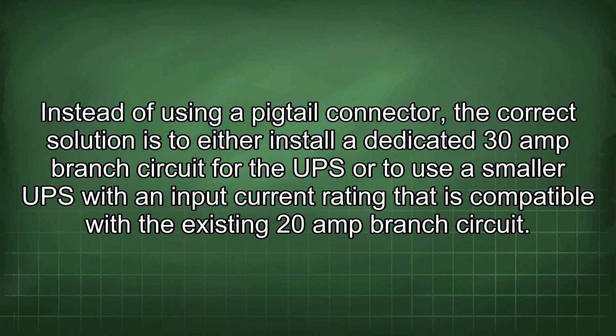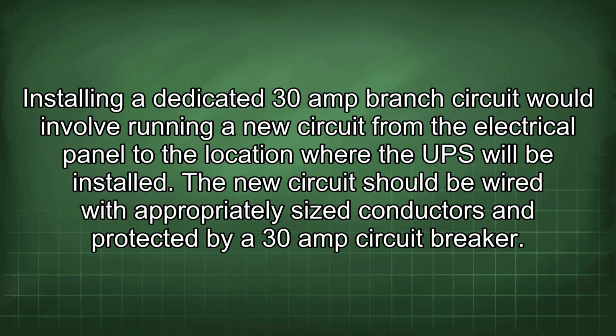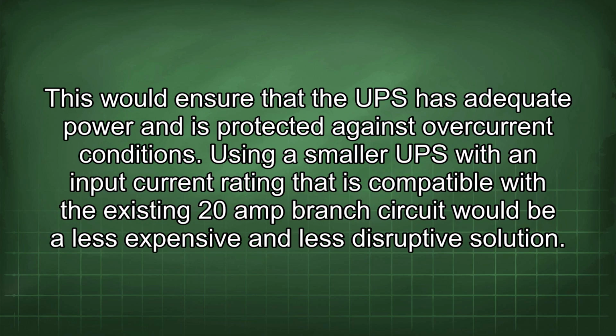Instead of using a pigtail connector, the correct solution is to either install a dedicated 30 amp branch circuit for the UPS or to use a smaller UPS with an input current rating that is compatible with the existing 20 amp branch circuit. Installing a dedicated 30 amp branch circuit would involve running a new circuit from the electrical panel to the location where the UPS will be installed. The new circuit should be wired with appropriately sized conductors and protected by a 30 amp circuit breaker. This would ensure that the UPS has adequate power and is protected against overcurrent conditions.